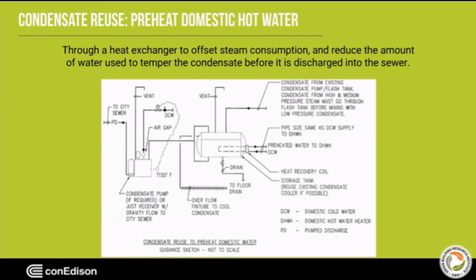This will not only offset steam consumption, but will also reduce the amount of water used to temper the condensate before it is discharged into the sewer. As shown in this sketch, this method requires a water-to-water heat exchanger, piping, and possibly pumps.